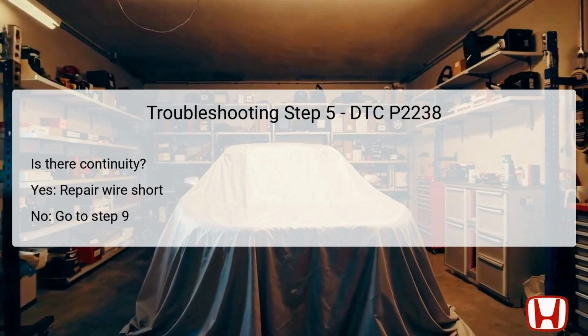Such shorts can cause erroneous low voltage readings and need to be rectified before any further steps are taken. It's an essential part of troubleshooting to ensure that wiring integrity is maintained. On the other hand, if the test indicates that there is no continuity present, proceed to step 9, implying that there may be another issue that needs to be examined in the system.